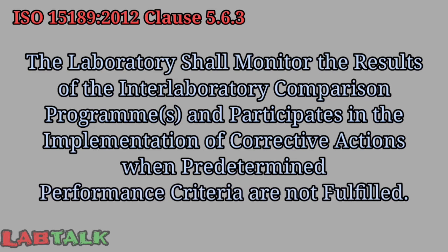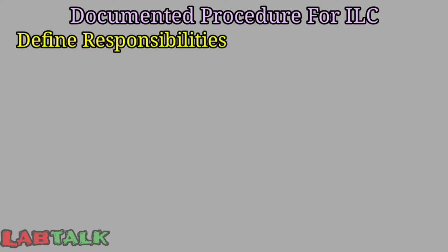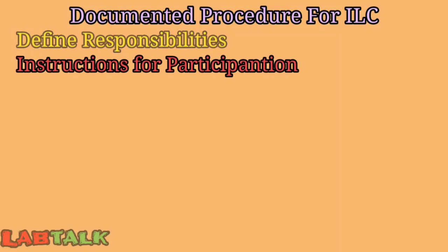So the international standard for the medical testing laboratory mentions that the laboratory should participate in an inter-laboratory comparison program. That should be as per the requirement of ISO 17043, which is a specific requirement for proficiency testing bodies. The laboratory shall establish a documented procedure for inter-laboratory comparison participation that includes defined responsibilities and instructions for participation, and any performance criteria that differ from the criteria used in the inter-laboratory comparison program.